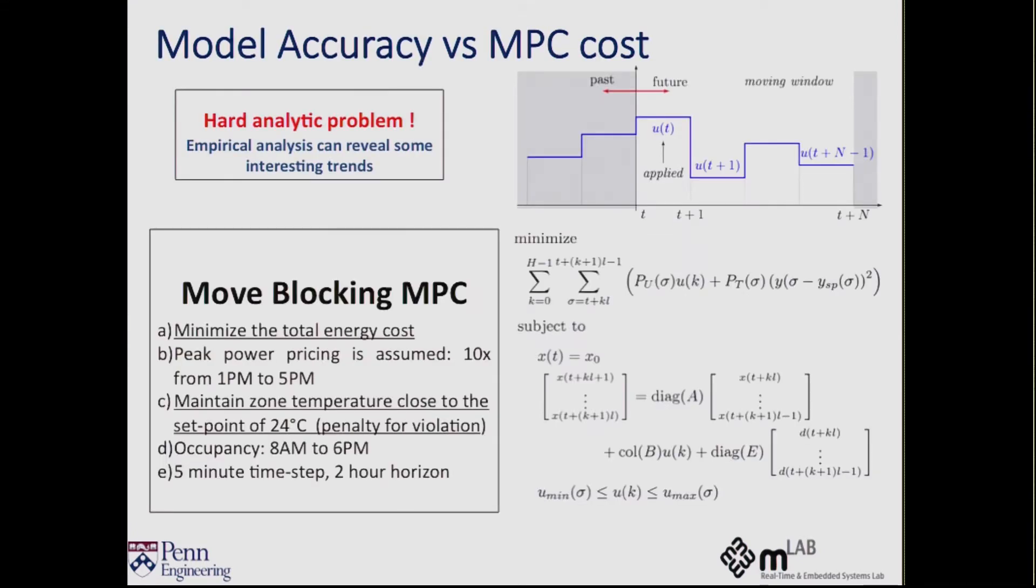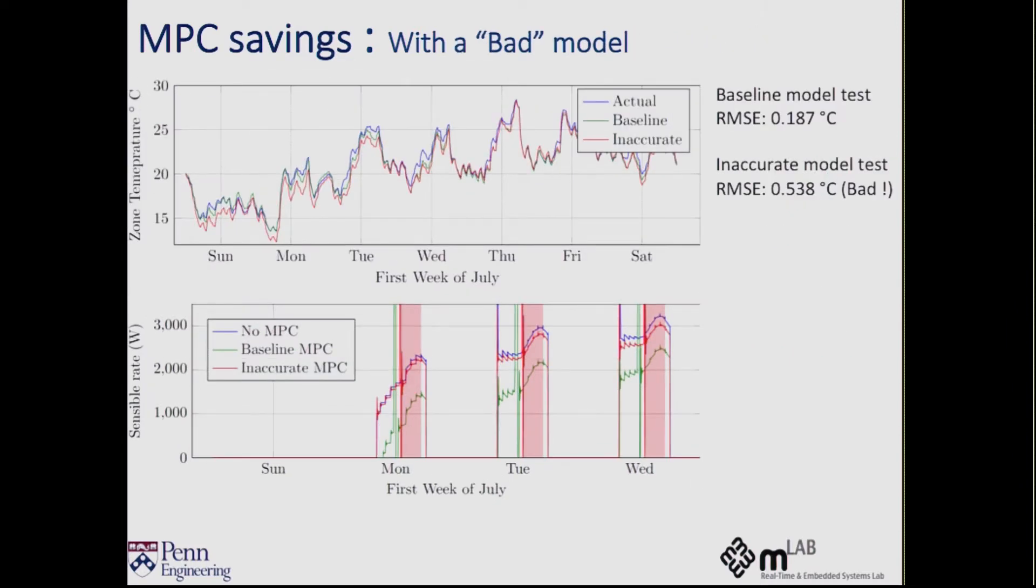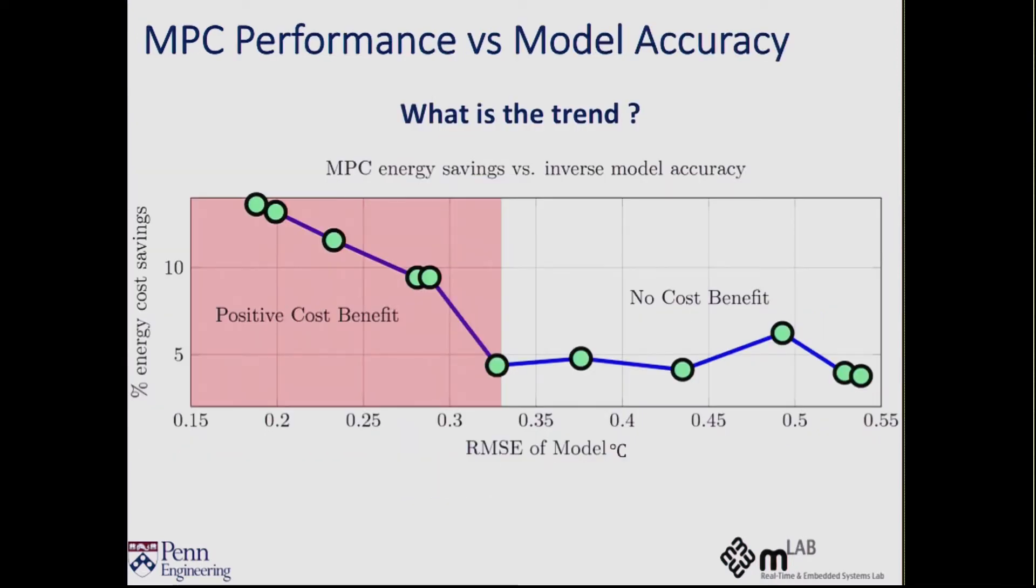So with MPC versus control performance, what we do is we do an empirical analysis in which the same model structure is used to implement a model predictive controller, in which the whole idea is that you want to minimize the total energy subject to some temperature comfort that you want to maintain with the model that you have learned. So it's very easy to implement in MATLAB. And what we do is you implement MPC first on the baseline model, which has a high accuracy and was trained on the original data with no uncertainty or whatever the regular data was. And it works well. You get about maybe 14% reduction in cost. And this reduction is happening because you're pre-cooling during peak hours. And then you deliberately give MPC a bad model, which has low accuracy, to throw it off. And you see that it does get thrown off and the energy savings you get decreased. So this is very intuitive. This is going to happen. But what we want to reveal is the trend.